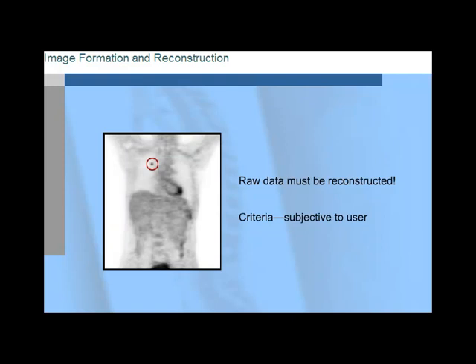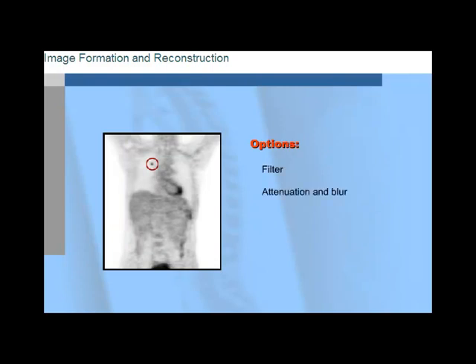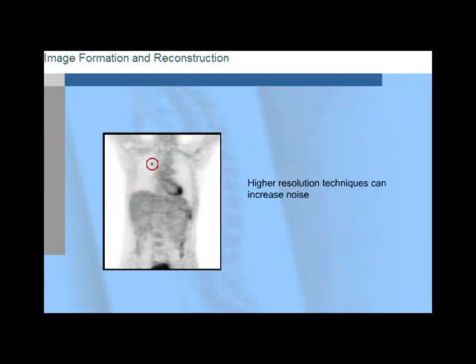Multiple factors influence which iterative reconstruction algorithm, or IR, to employ in PET imaging. Reconstruction options include choice of filter, attenuation and blur, weighting, comparison by ratio and difference, and the number of iterations. While sharper filters and larger numbers of iterations offer higher resolution images, they also increase noise. Smoother filters reduce the noise level, but then the image resolution isn't as high.